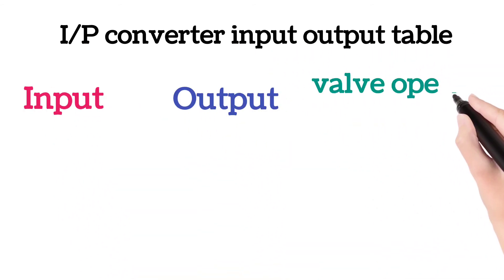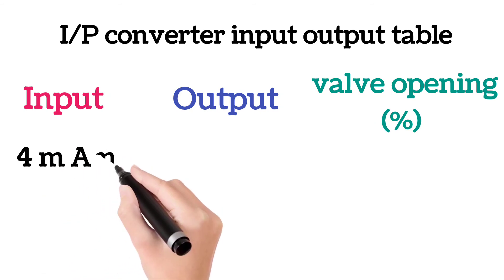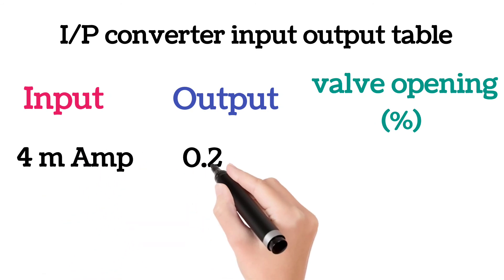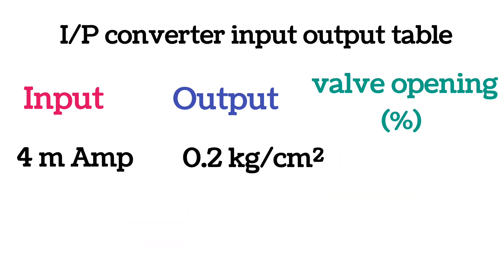Now we will see input and output table for an I to P converter. At 4 milliamp signal, the output of I to P converter is 0.2 kg per square centimeter and the control valve opening will be 0%.